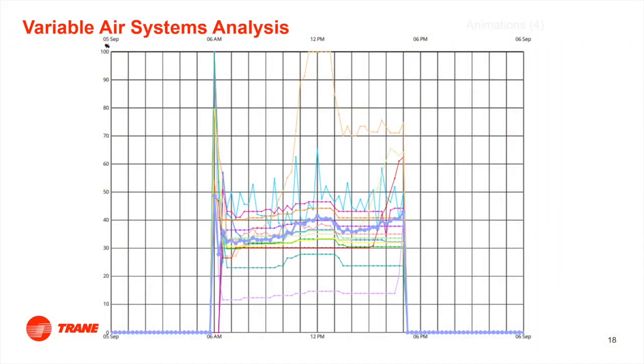Now this is another chart—love charts, I can tell everybody loves charts. But anyway, this one is very simple. This is the valve position of all the VAV boxes served by this air handler. Do I really care what their names are? I do not. I care about where the average is. You can see right here, all the VAV boxes are sitting at about 35%.